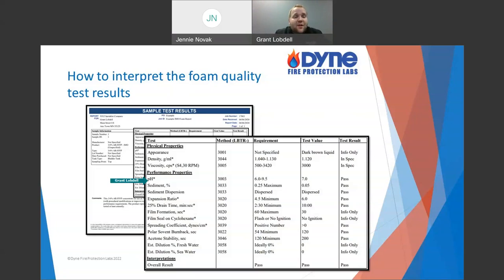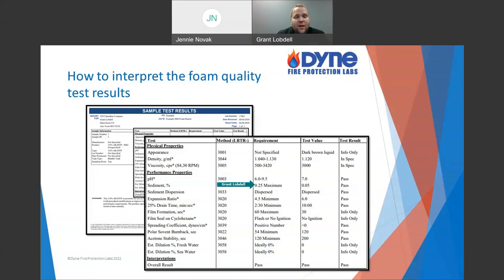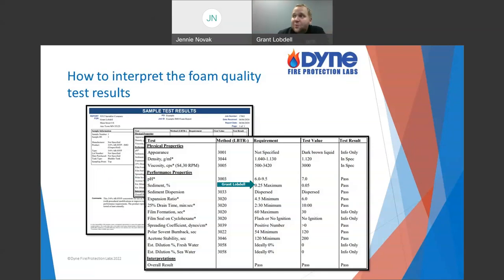For performance properties, it's simple: either it meets the specification or it doesn't, and the report will say pass or fail. Sediment — shown on screen — has a maximum specified by IMO; not required in NFPA, but IMO requires you to be below a certain percentage. Why would sediment be high? You just have some crud in the system — maybe the tank or trim pipe is corroding. Make sure when taking samples, everything I do and what I put on this report is only as good as the sample you give me.